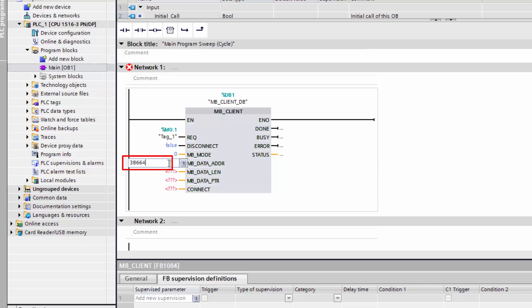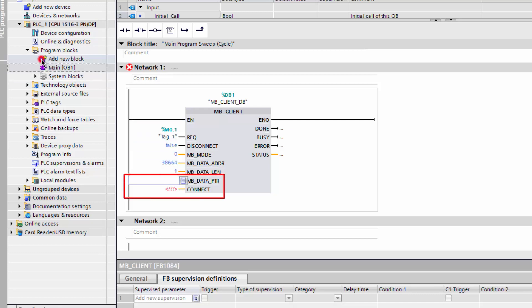The number of registers must be entered in the MB_Data_LEN field. This status information of the device occupies one register. The parameter MB_Data_PTR denotes a pointer to a data buffer for the data to be received or transmitted.